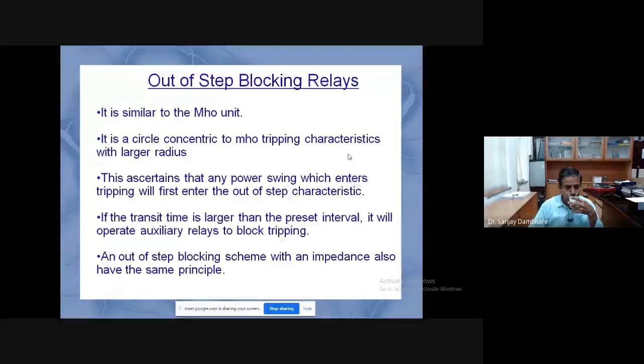These are nothing but power swing block settings. What the relay does is monitor the travel time from one location to another. If this travel time is very slow, the relay declares it a power swing and is not allowed to trip. The relay is put in a block region.